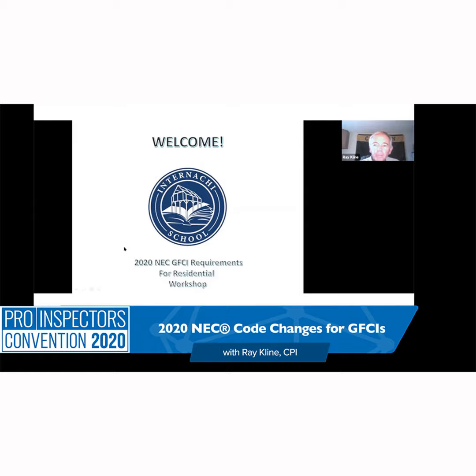According to the NEC, and I'm going to use the NEC quite a bit in here, which stands for the National Electrical Code, a ground fault is a conducting connection, whether intentional or accidental, between any electric conductor and any conducting material that is grounded or that may become grounded. Electricity always wants to find a path to the ground. It always wants to return to the source. In a ground fault, electricity has found a path to ground that it was never intended to be on, such as through a person's body. Because of the potential for shock, GFCI protection is used to protect human life.